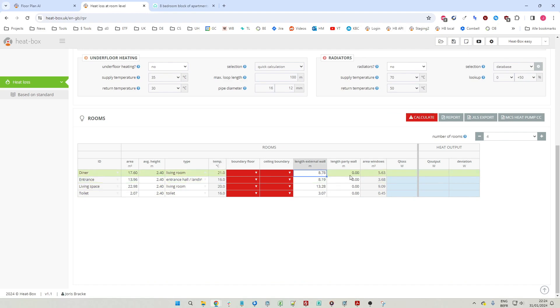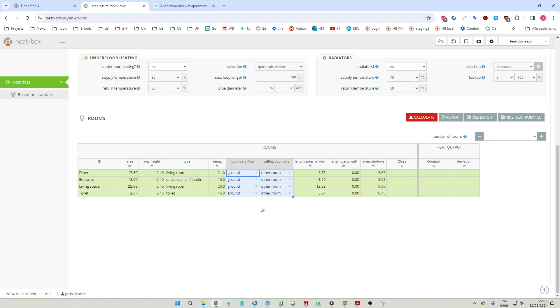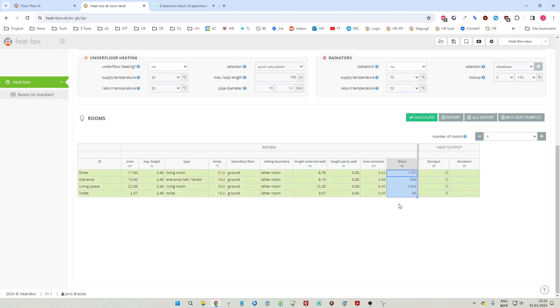Then we have the length of the external wall, length of the party wall, and surface area of the window. The only thing we still need to add manually is the boundaries for the floor and ceiling. Let's say the boundary of the ground floor is ground and the boundary of the ceiling is the other room. We draw down these cells just like we would in Excel, then hit the calculate button to calculate heat loads for the different rooms. If we do this for all floors, we can also calculate heat loads at building level.